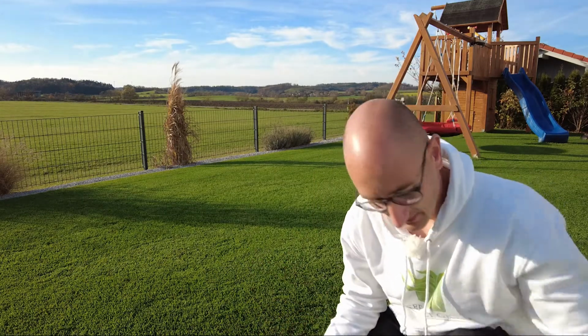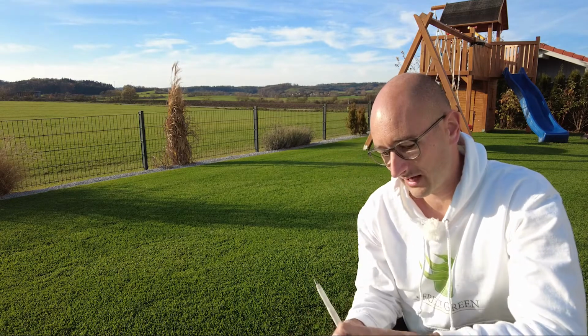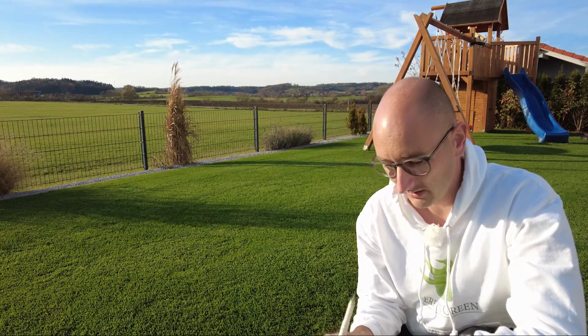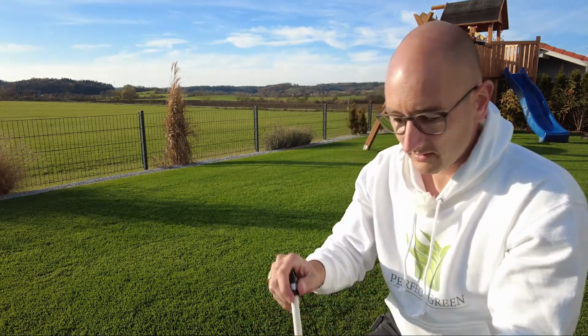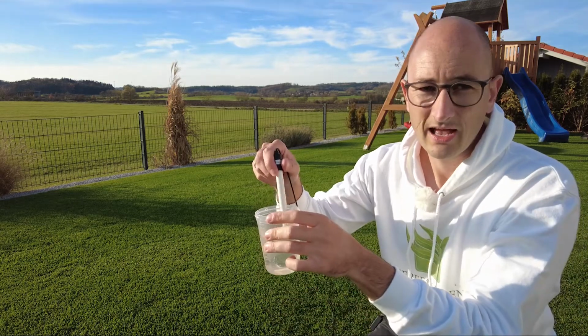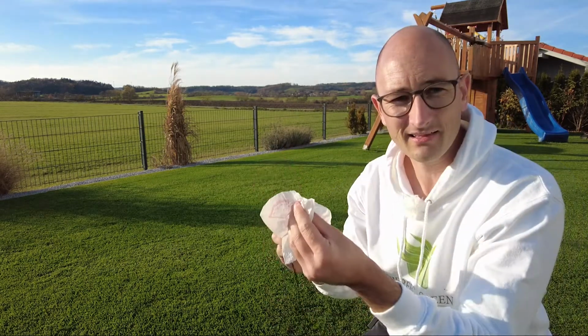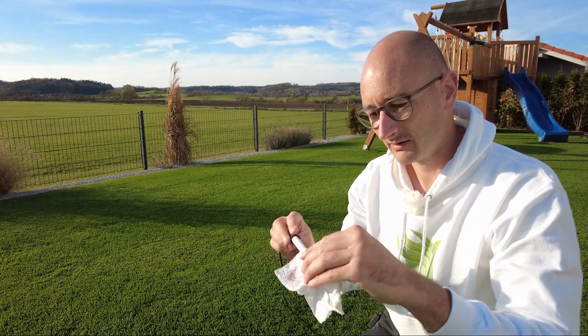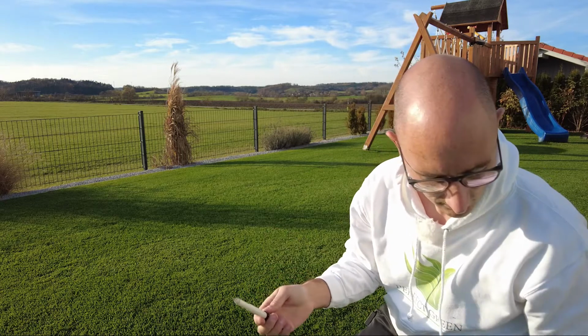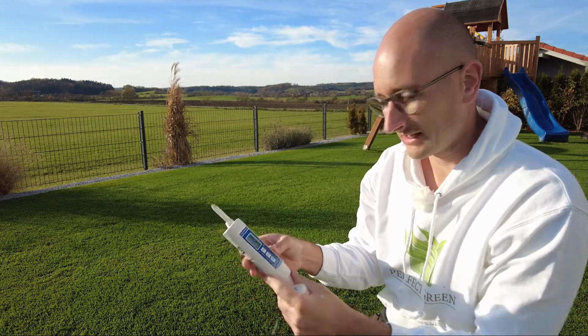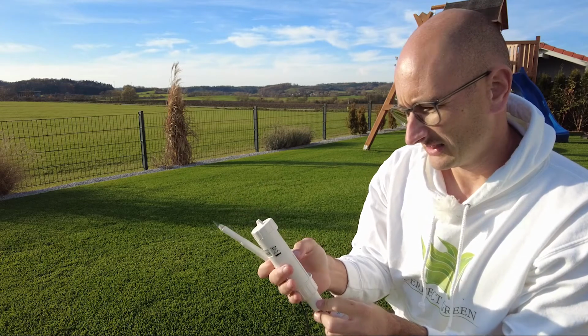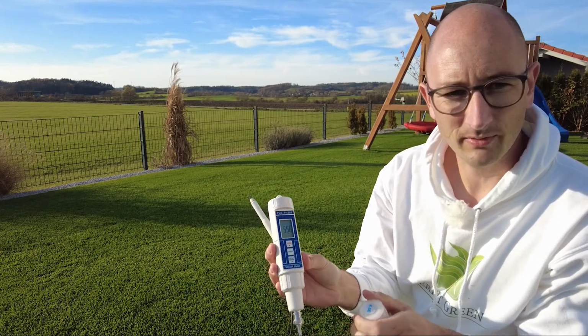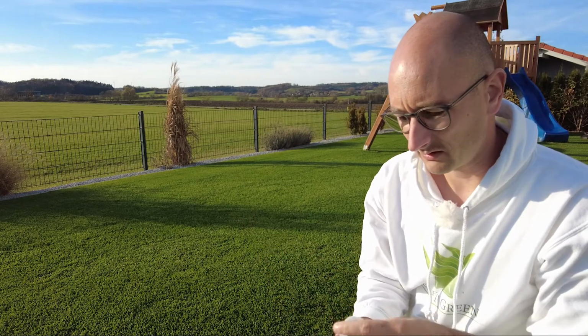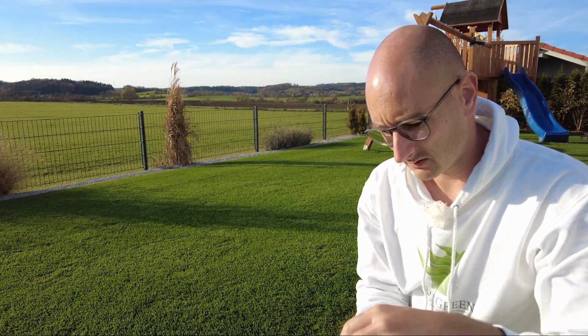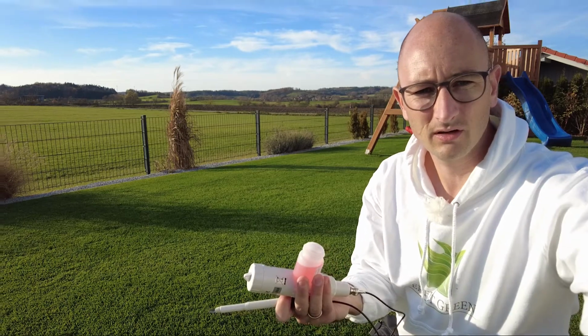Before you start, for example to test it, you should calibrate it when you receive it for the first time. First you have to clean the storage solution off it. I clean it off carefully with kitchen paper. And as you see, I turn the device on. It shows 6.0 at the moment. This is the storage solution, pH 4.